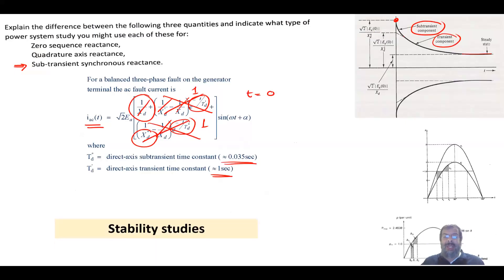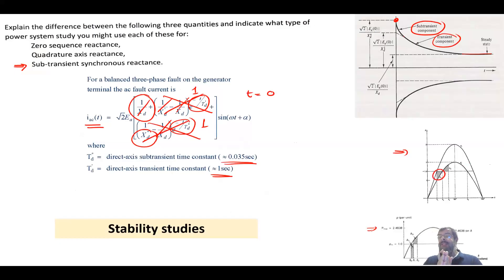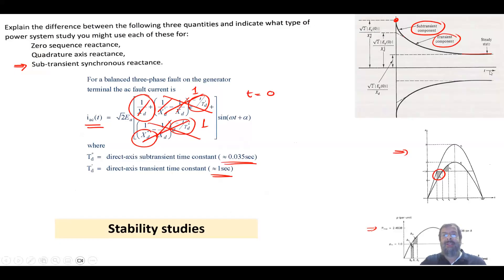One application where the sub-transient reactance is used is in stability studies. The equal area criterion shows that how quickly a fault is cleared determines whether the system remains stable or goes unstable. The fault must be cleared as soon as possible before the accelerating area expands beyond the decelerating area. If the system becomes unstable, the rotor accelerates indefinitely, synchronization is lost, and the result is a blackout.